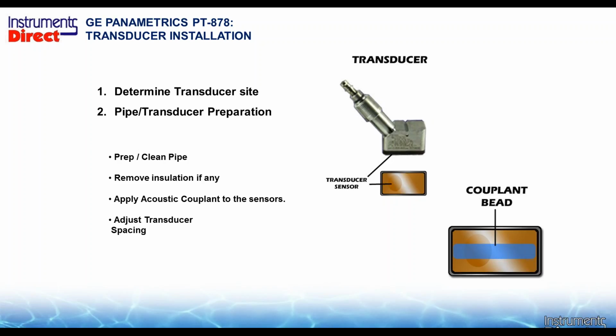The transducer is flat, the pipe is round. We need a conduit to send the sound beam from the flat sensor to the pipe wall. So we put a bead of acoustic couplant. How much? Toothpaste on a toothbrush. That's all you really need there. We don't need to goop this thing up there.